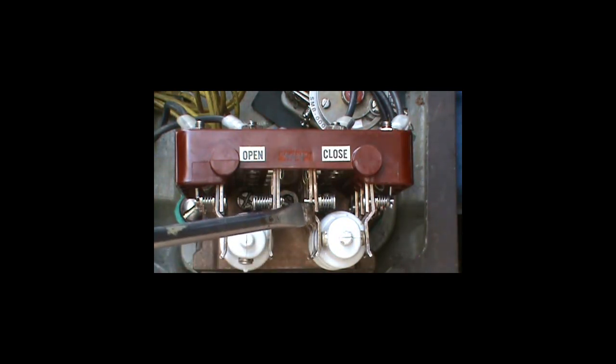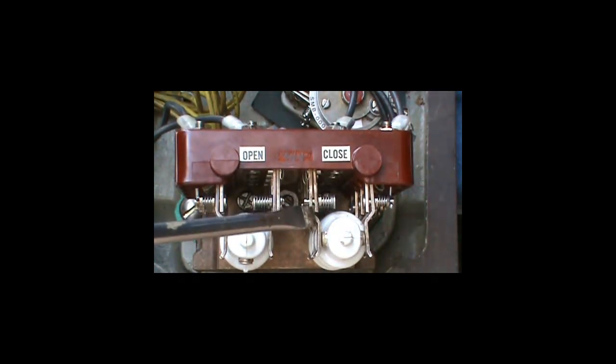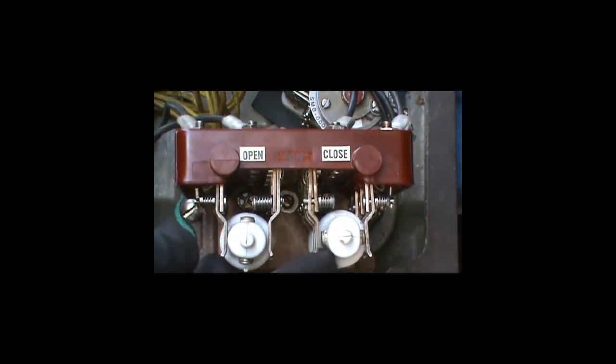there should be a gap here between the L-bracket and the contact finger. See how there's an air gap between the L-bracket and the contact finger? That means the spring is putting some pressure on the finger to the contact.